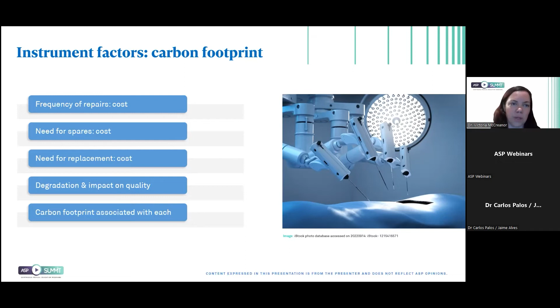I can talk to you about the costs and the reduction in repairs you might see from changing, if you have those types of devices, from steam to a low temperature system. This is taken from a paper - you can see the reference in the slide - where in a hospital, I think in Germany, they were using a steam sterilizing system and moved to a low temperature system. They recorded all of the different types of damage that occurred, how frequently that happened, and the types of damage, then recorded the same thing after changing to the low temperature sterilization system.